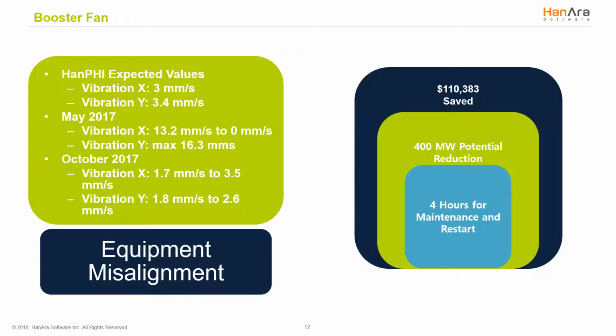In May, HanPHI detected an anomaly in the booster fan vibration. Vibration X fluctuated from 13.2 millimeters per second to 0 millimeters per second when HanPHI expected the vibration to be at 3 millimeters per second. Vibration Y also fluctuated, reaching a maximum of 16.3 millimeters per second when HanPHI expected the vibration to be at 3.4 millimeters per second. Though vibration X and Y were fluctuating, the fan inboard vibrations were normal. The manufacturer inspected the instruments, sensing lines, and terminal block, but did not find anything. The site assumed that electrical cable damage had caused the malfunction and decided to replace it during the next overhaul.